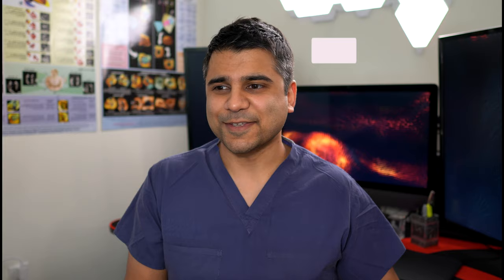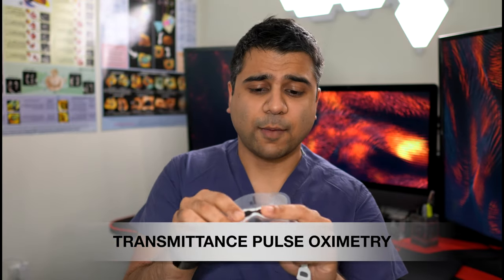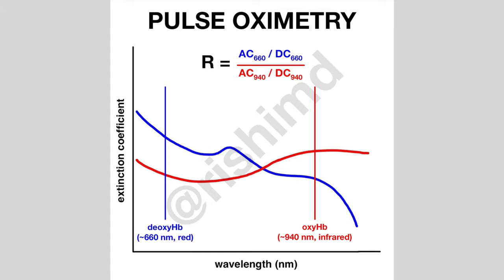But what really has me concerned is the term 'blood oxygen' for a device that's essentially a pulse oximeter. Now in the hospital we're used to seeing these things. Typically these pulse oximeters are affixed to the fingertip and they provide transmittance pulse oximetry, which basically means that when they are properly affixed, the light source on one side is transmitting various wavelengths of light through the tissue and photodiodes on the opposite side are picking up how much light was transmitted. So 660 nanometers and 940 nanometers are the two big ones — corresponding to the visible red spectrum and the infrared spectrum.